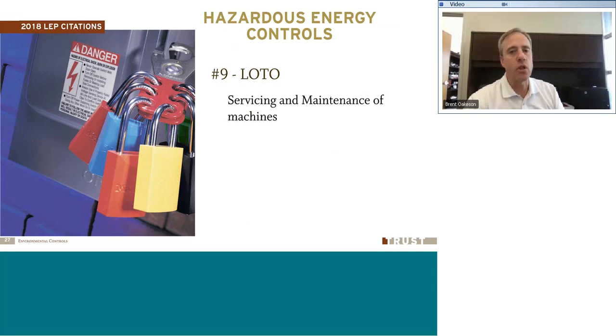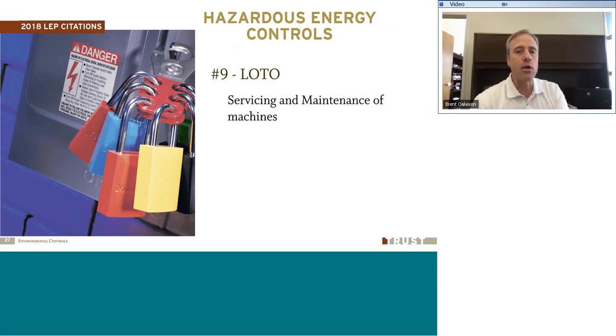With your lockout tagout program, they're looking at whether we have a method for putting equipment in a safe state while it's being maintained or serviced, or making sure equipment not safe for use is taken out of service so it can't be used dangerously. The lockout tagout requirements specify that we need to do an assessment on each piece of equipment and a lockout tagout procedure for each, identifying the steps needed to make sure the equipment is de-energized from any potentially hazardous energy source.